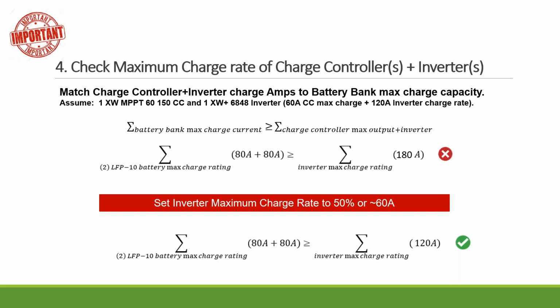So you want to make sure, again, that the battery bank's maximum charge current, grouped together, can handle the combined charging rate from the charge controller and inverter. Because the way the inverter and the charge controller work is, if the battery bank goes too low, then you have solar to charge your battery. At the same time, the inverter can also charge your battery. Of course, if you do not want inverter charging, you can turn it off. But most likely you want to have that, because that way the battery bank can be charged quickly.